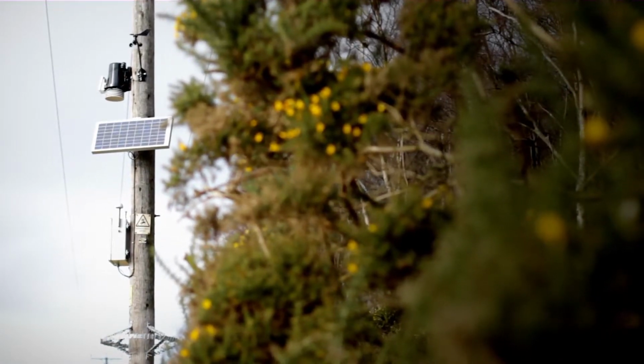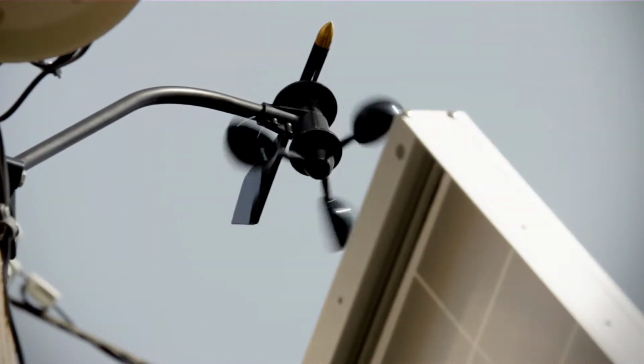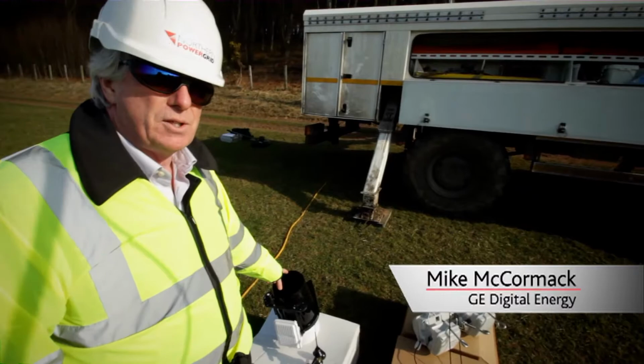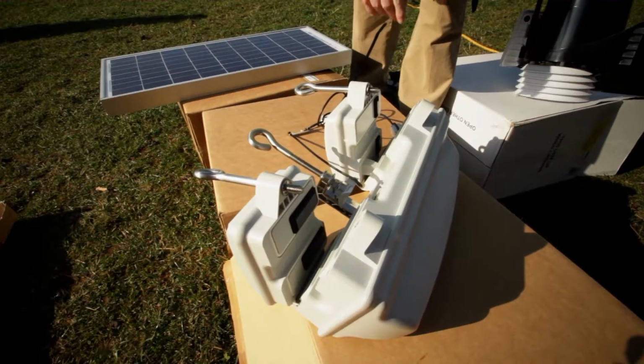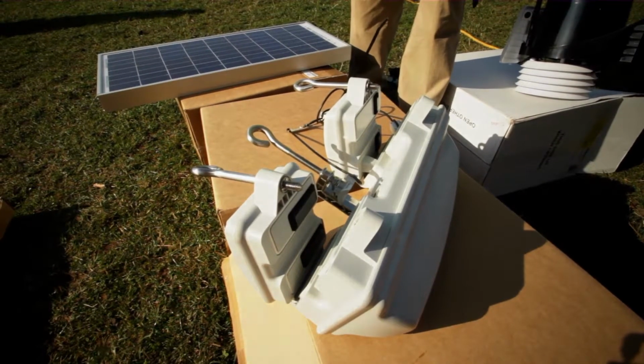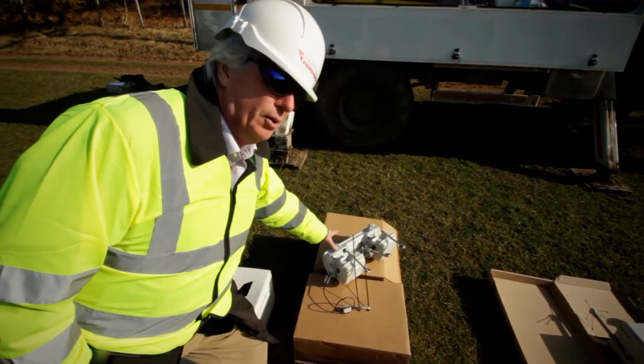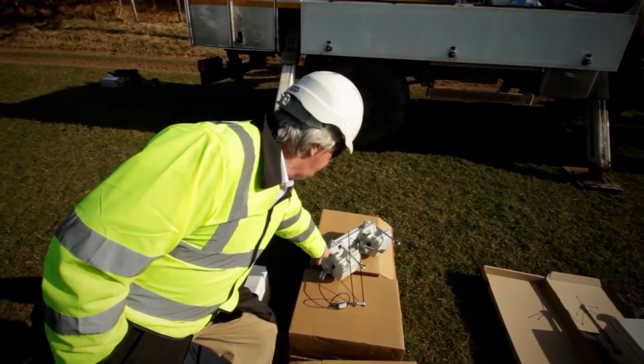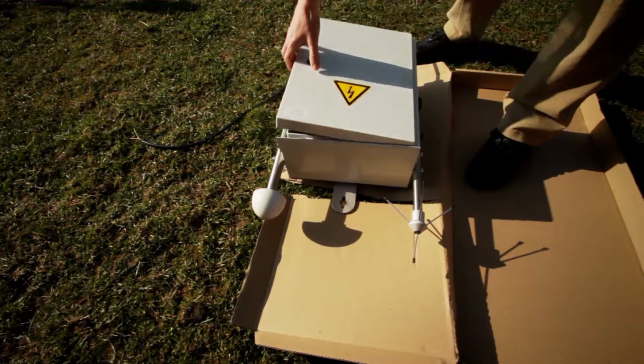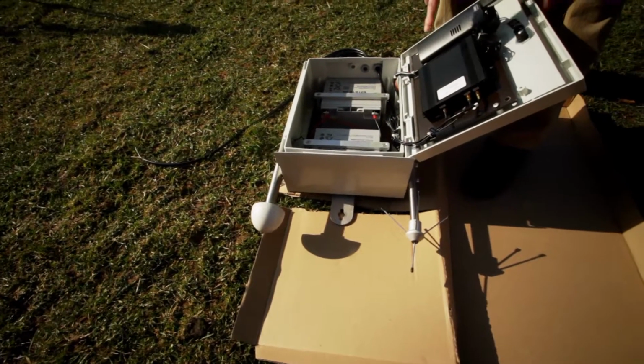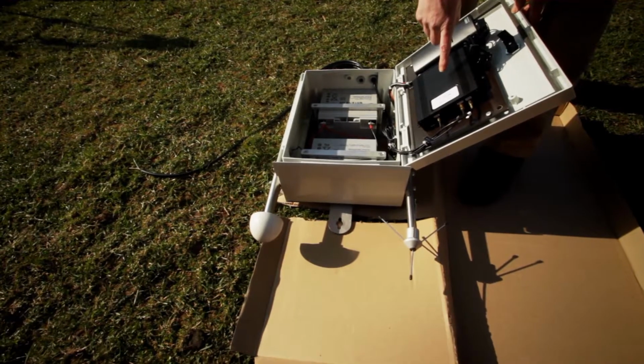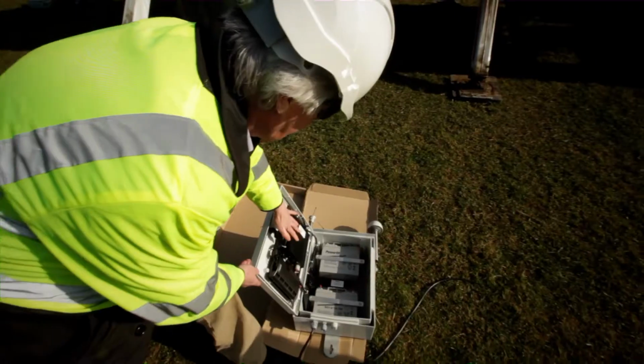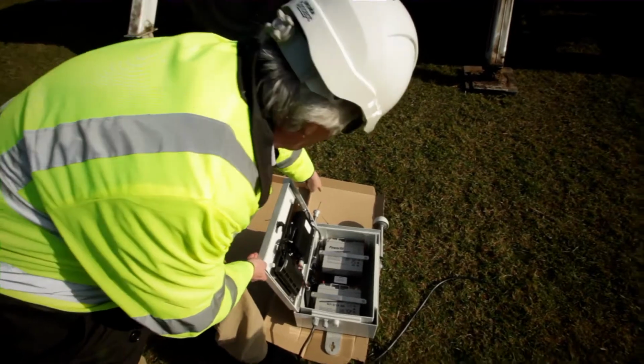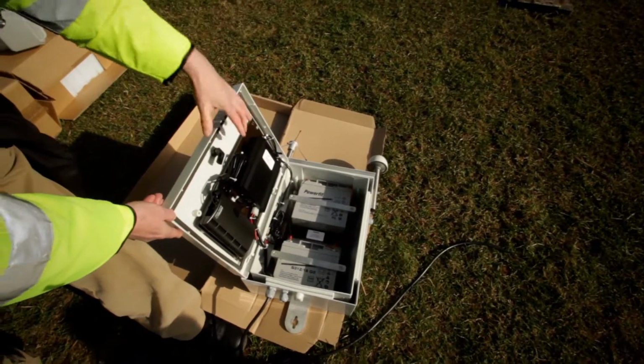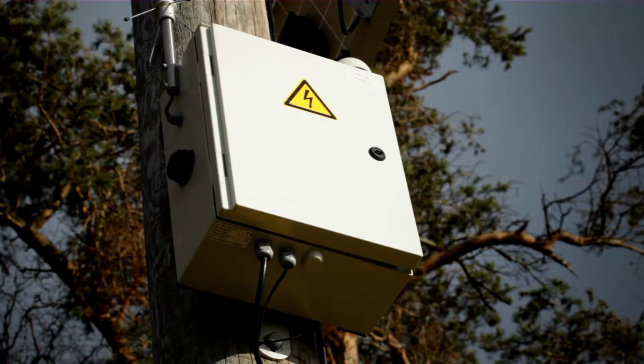This one in particular is a prototype in essence, but it's been proven in Northern Ireland. This is the weather station, a standard off-the-shelf weather station, and this is the actual power line sensor. This is the FMC sensor, and it measures the current on the conductor via a CT here, a current transformer. This is the controller, made up of an SNG, a sensor network gateway, which is the device that captures the information via radio from the power line sensors and forwards it by GPRS back to the server.